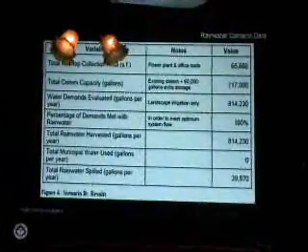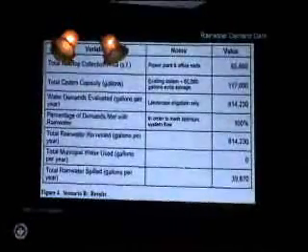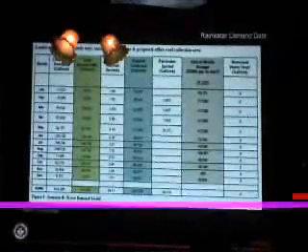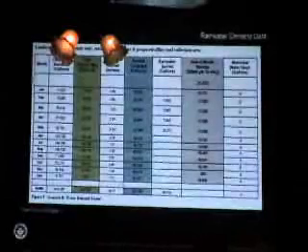Okay. So you run a model and you calculate these things. We had 75 years of daily rainfall records, and we looked at the different types of months over that period, so it's 75 Januarys, let's say, and you look at the different size of rainfall events, and you assume something like 10 gallons per 1,000 square feet of roof area will be taken away and flushed and not put into the cistern because it'll have debris in it.